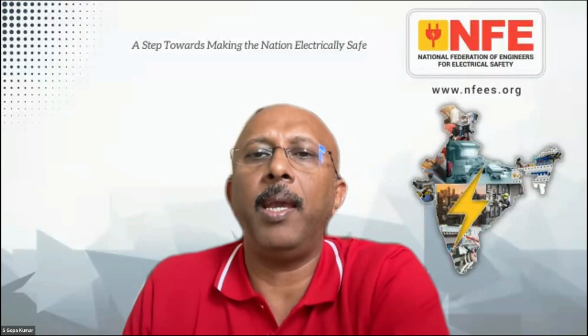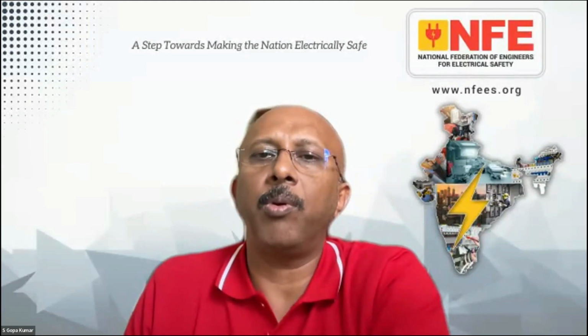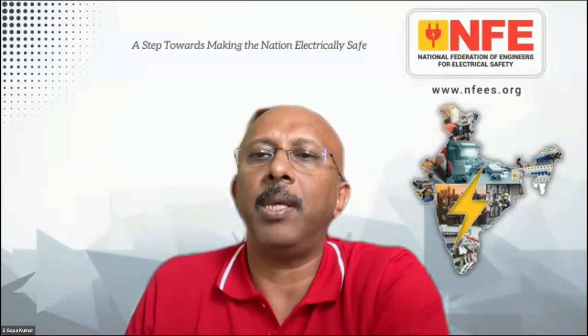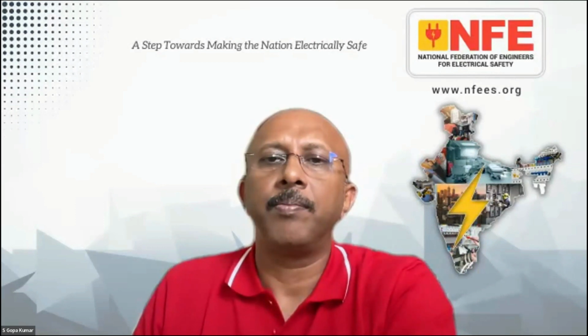If 10.5 kA is the short circuit of a 500 kVA DG, what is the capacity of Icm and Icu of the breaker? Sorry, let me just read that question again. If 10.5 kA is the short circuit, well, obviously you would need a breaker to have... Icm is not really that important here, and Icu is also not important. And Ics of greater than 10.5 kA. So Ics is important, not Icm or Icu in this situation. Ics has to be greater than 10.5 kA. Okay. And 10.5 kA is a very easy value; you can get 16 ampere breakers with that Ics easily. That's not a problem at all.